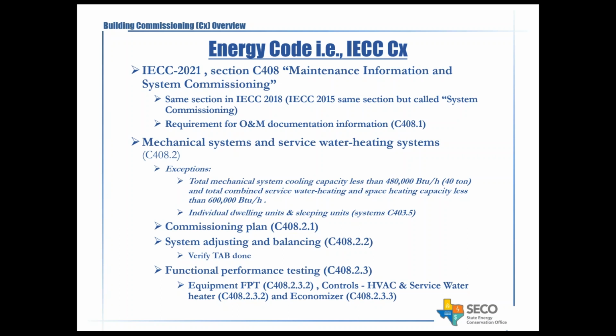So this is a good question. What is the minimum size that I need where I have to have commissioning in place? Of course, you can have commissioning without any minimum size, but if you're just concerned with what the code requires, then the code requires commissioning on all buildings, with the exception that you have a total mechanical system cooling capacity of less than, I'll just say, 40 tons of cooling capacity, and a combined service water heating and space heating capacity of less than 600,000 BTUs per hour. And then individual dwelling and sleeping units are exempt.